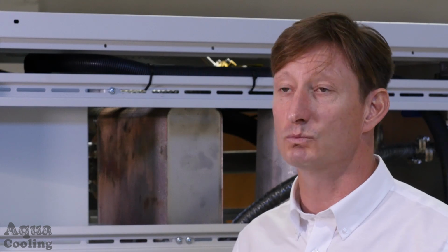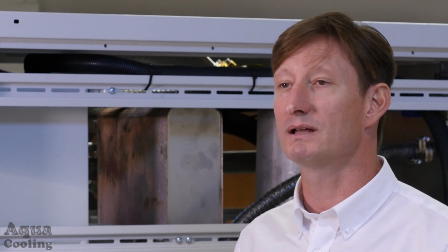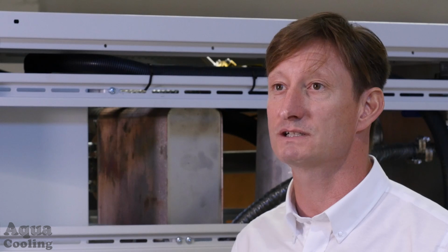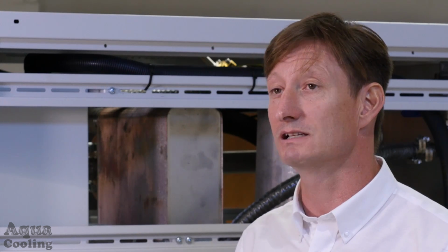One of the reasons we looked at the rear door cooling is we can get more IT load within the cabinet, and we use variable valves on that, so it changes with whatever load we're putting in there. And it can be high density computing in there like the HPC. The advantage of using the LPS and a water cooled based system allows you to use natural forms of cooling, so we can use river water, sea water, borehole water, or even cooling tower water, which allows you a much greater efficiency and in some data centres actually eliminate the use of refrigeration totally.